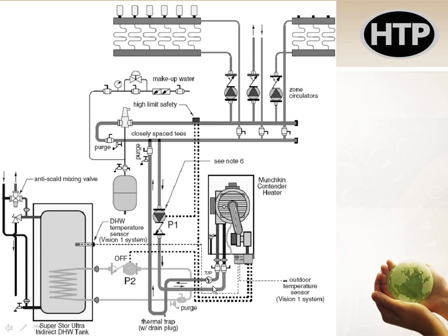The other cool thing we're showing on this drawing here, over on the left-hand side, we have an indirect storage tank on there. That basically is a very nice water heater tank, if you will. Instead of having a burner in the bottom of it, it has a hydronic coil, and I'm able to take water from my boiler, send it through that coil to heat up my domestic water. The water is not the same. They don't touch. I have my domestic water separate from my boiler loop water, but I run a coil with that boiler loop water into that tank just to warm up that water. So I can get rid of that fairly inefficient gas burner that's in a water heater, and now in this example, I'm using a 93% boiler to heat my domestic water as well.